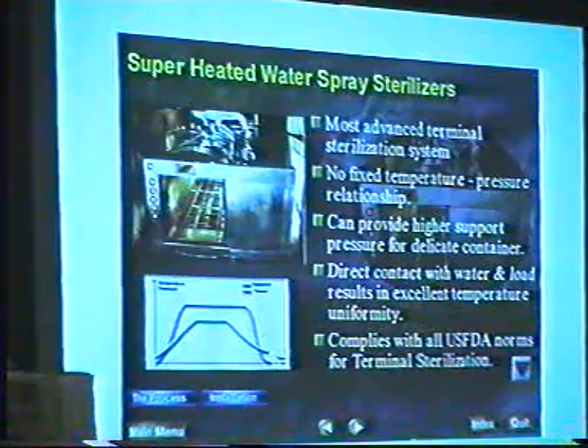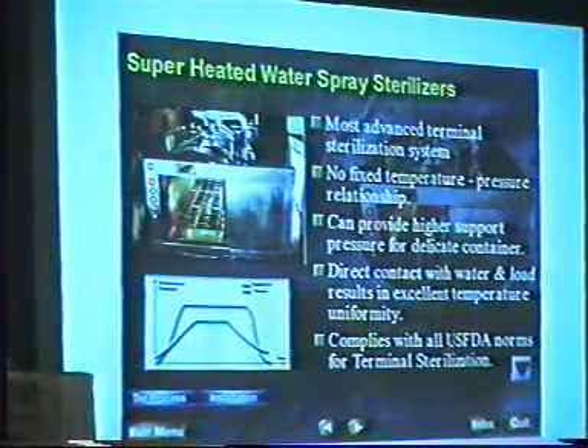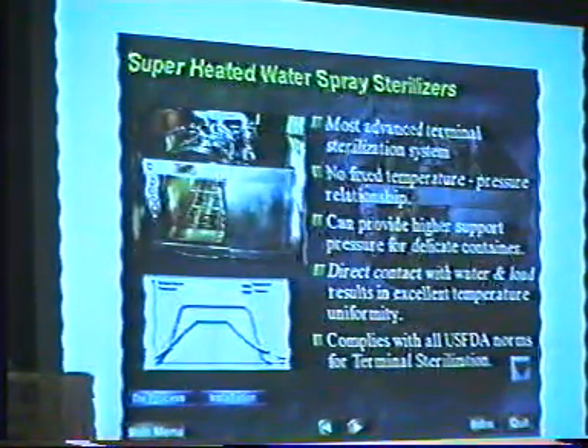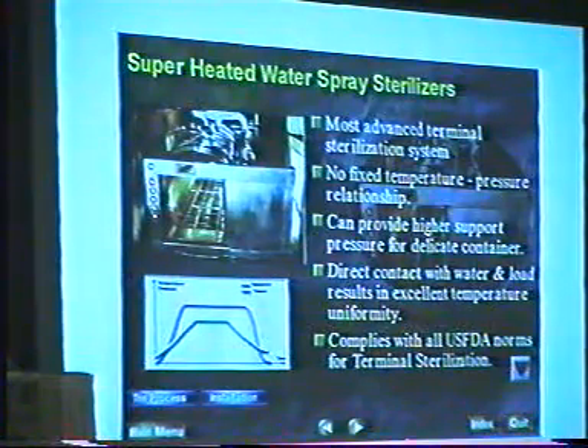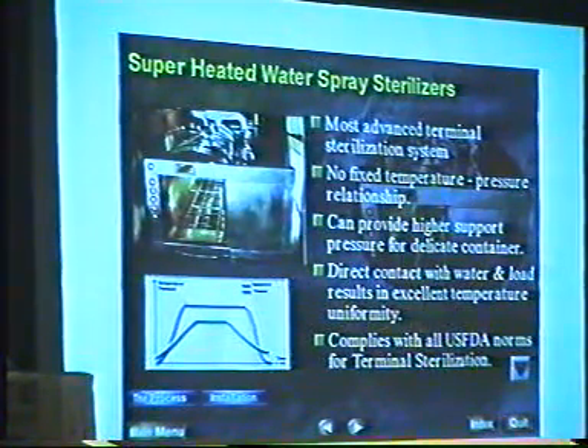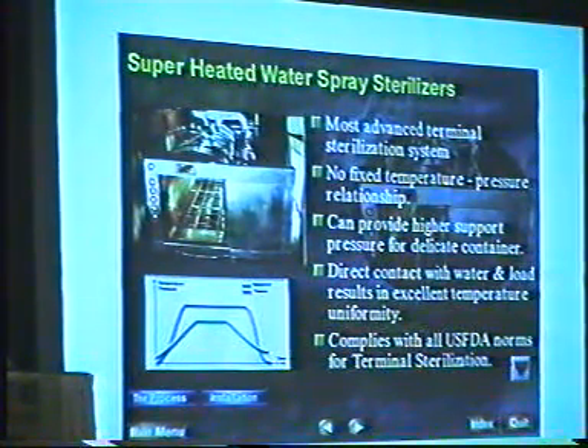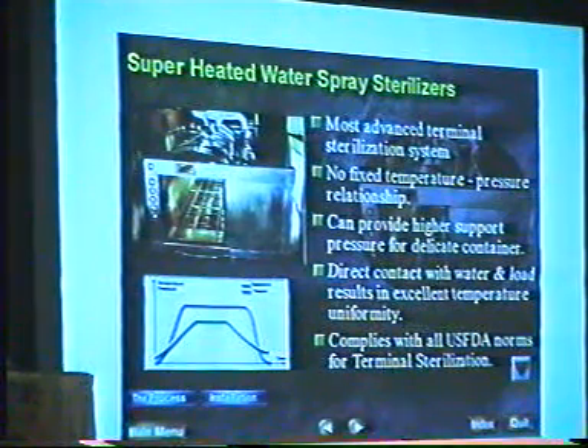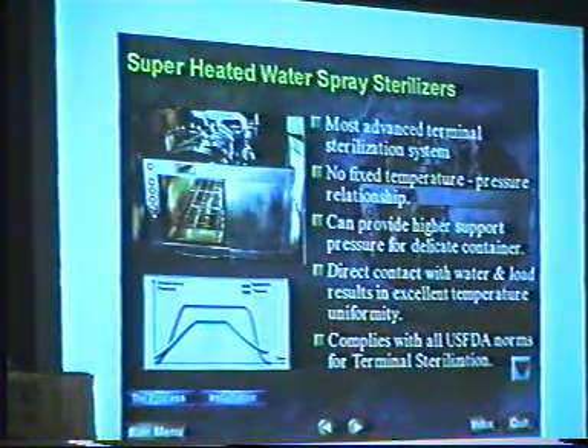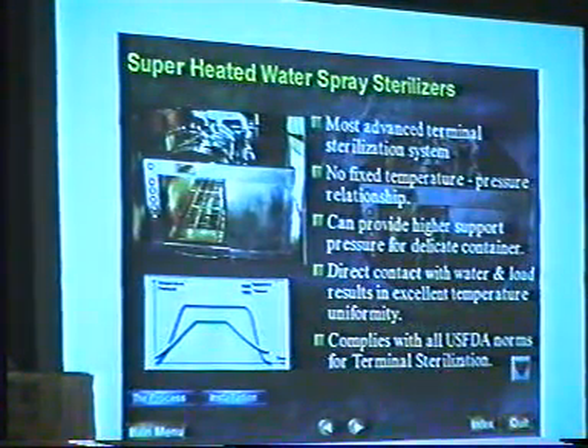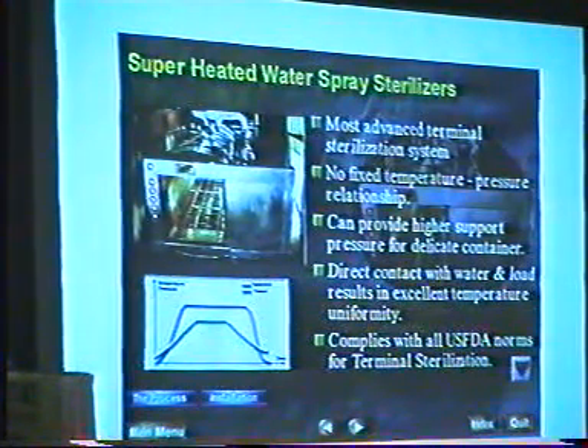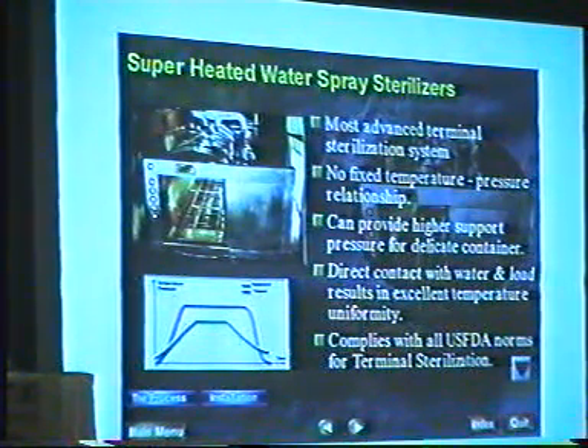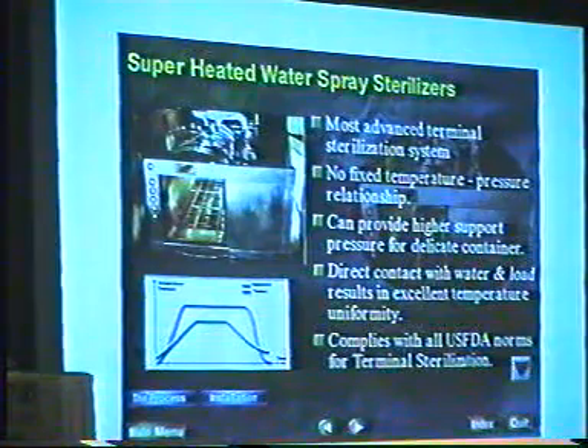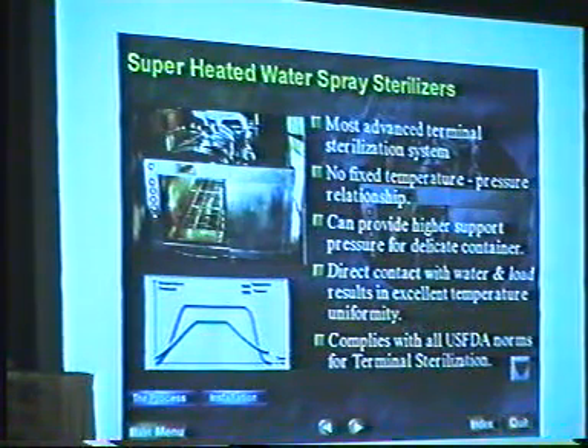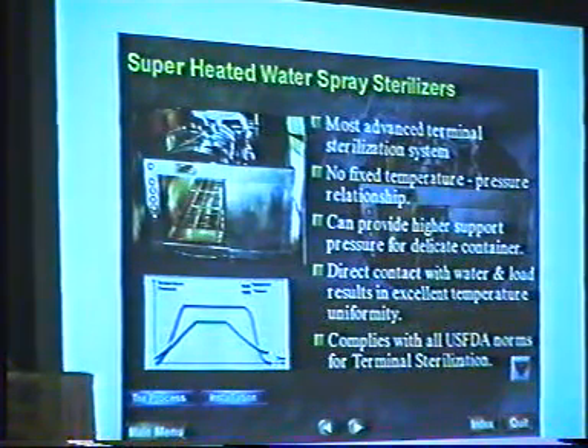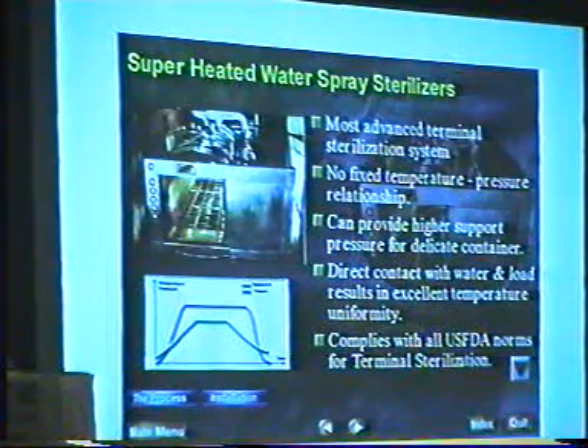Now let us look closely at how these two systems work. Let us take up the superheated water spray sterilizer first. As you know, when you are operating a conventional steam sterilizer, steam is your basic sterilizing medium, and steam always follows steam tables. So whatever temperature you want, there will be a certain pressure which is its natural pressure. You cannot have that steam at that temperature with any other pressure.